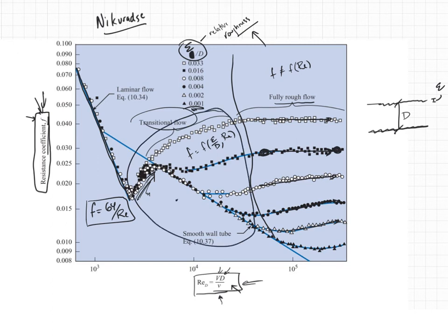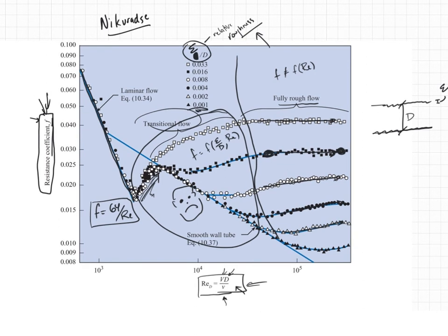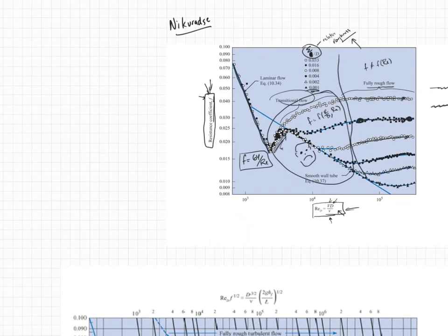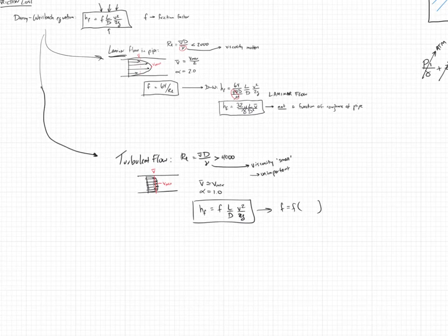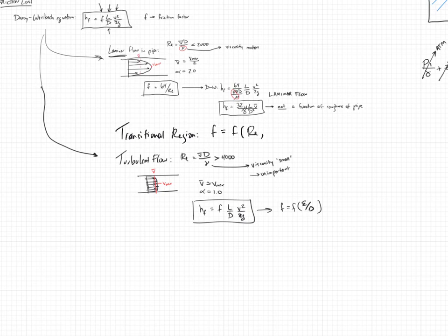Once you get into fully rough flow — way over to the right where the lines go flat — F is no longer a function of Reynolds number; it's only a function of relative roughness epsilon/D. So in this complete turbulence region, F is a function of epsilon/D only. In the transitional region, F is a function of both the Reynolds number and epsilon/D. The fully turbulent region is very easy to work with. The transitional region is the difficult one — you're unhappy there.